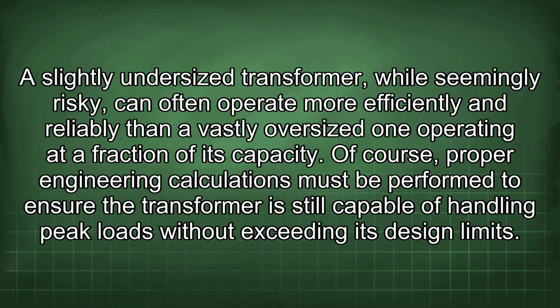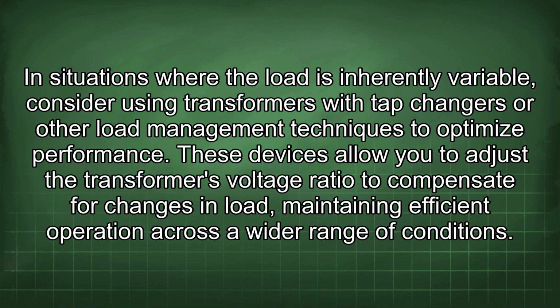A slightly undersized transformer, while seemingly risky, can often operate more efficiently and reliably than a vastly oversized one operating at a fraction of its capacity. Of course, proper engineering calculations must be performed to ensure the transformer is still capable of handling peak loads without exceeding its design limits. In situations where the load is inherently variable, consider using transformers with tap changers or other load management techniques to optimize performance.